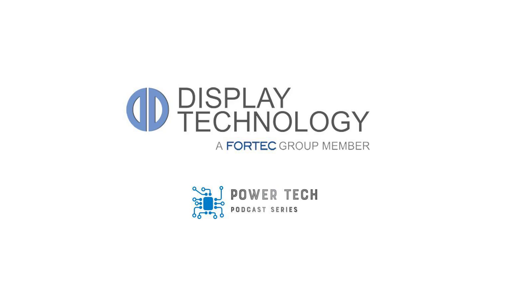Undervoltage protection, UVP, works by continuously monitoring the input voltage, and in the event that the voltage drops below a predetermined threshold, it shuts down the converter to prevent damage to the components. Low voltage can result in a decrease in power output, which can affect the performance of the connected devices. Furthermore, prolonged undervoltage conditions can damage the converter, potentially leading to costly repairs or replacements.